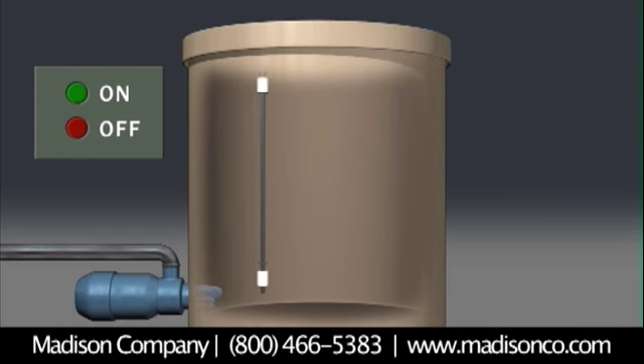Multi-level float switches from Madison Company are used to control pump up and pump down operations where liquid level accuracy is critical to the performance of the product. As the liquid level in the tank rises, the float or floats travel along the stem within a designated travel or activation range, which is typically half an inch. When the water reaches the pump-on activation point and the float rises, the pump will automatically turn on to empty the tank. When the tank level drops below the pump-off activation point, the pump will turn off. This cycle will repeat as often as required and requires no manual intervention.